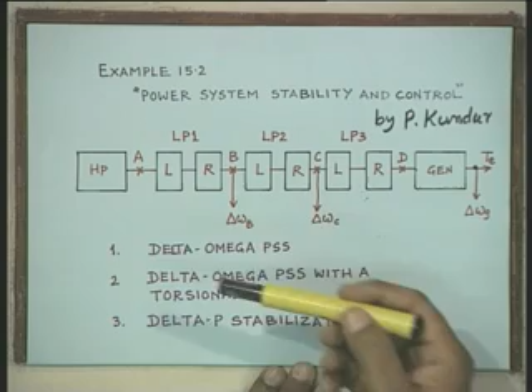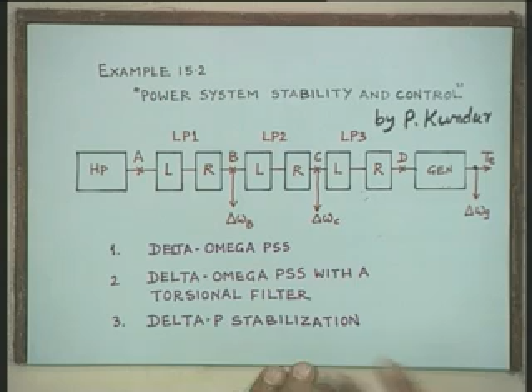Studies show that if you have delta omega PSS only, without a torsional filter, then as you increase the power system stabilizer gain, some of the torsional modes will get excited or have negative damping. Further studies showed that the moment the torsional filter is incorporated, the chances of excitation of torsional modes are eliminated. Further, when delta P stabilization was put, the results obtained were similar to the second case, where delta omega PSS with a torsional filter was put. All the details are given in example 15.2. I suggest the interested readers go through this example in detail.